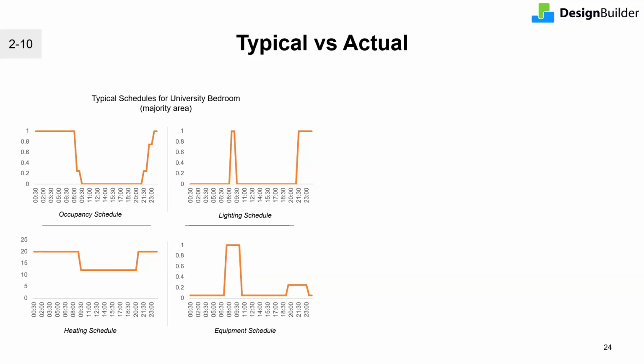When we start modeling, we use typical operational profiles defined in common standards for occupancy, loads, and operation profiles of various things. Here are the schedules for a student accommodation bedroom space from a typical database, which reasonably assumes that there is occupancy during evenings and no occupancy during the day when students are in lectures. So in most scenarios, these operational assumptions feel realistic.